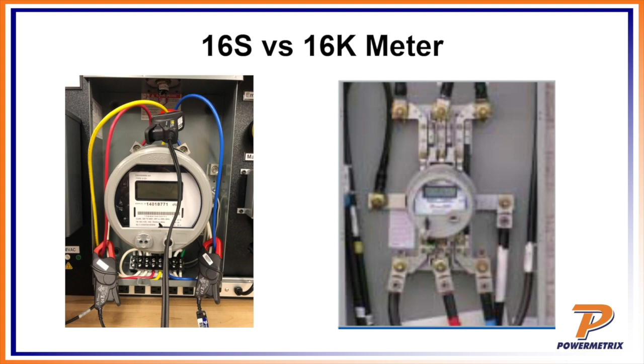So tell me about your experience with K-base when you were at the utility board. My biggest issue was seeing them not torqued correctly, they used to come with little torque wrenches back in the day. I've also seen cases where a customer says their service is 380 amps, they've added a couple things like freezers, and you come back, take the lid off the meter, and see the legs have started to discolor a little bit.